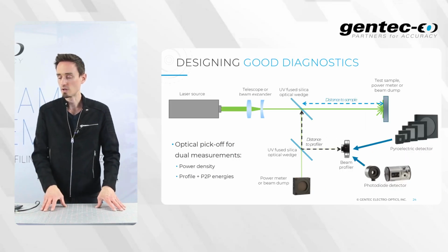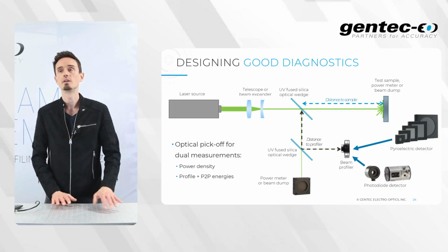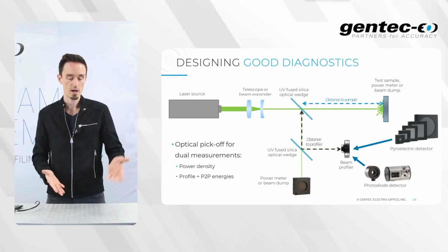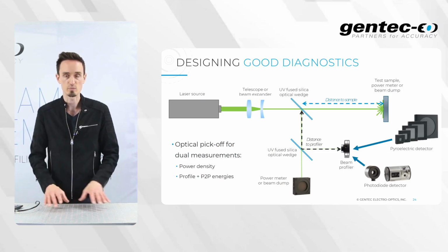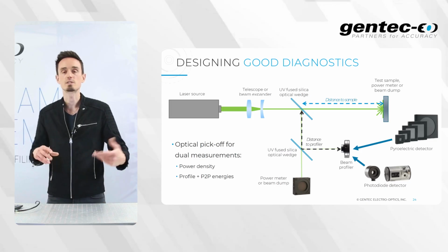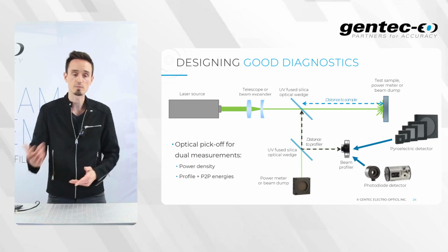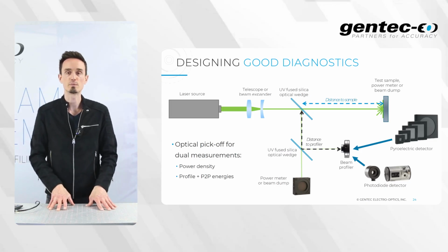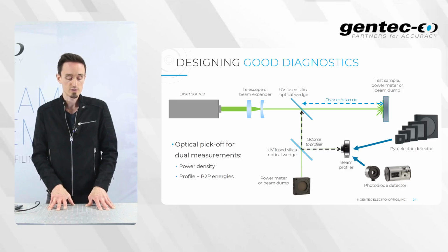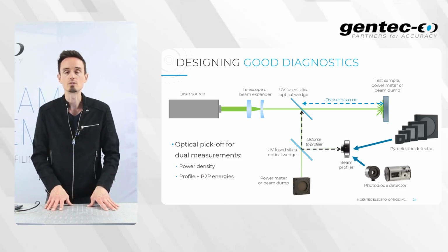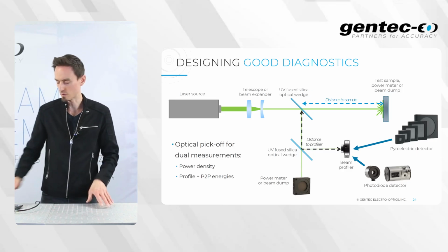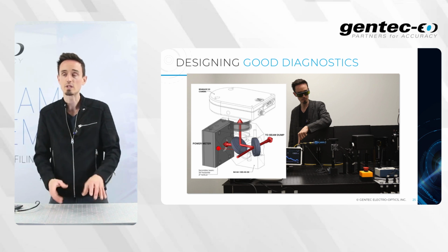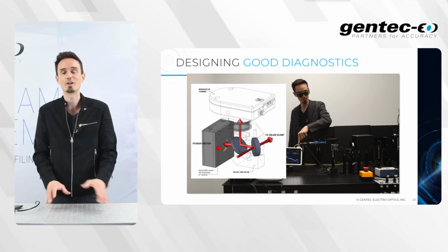An example of a good optical pick-off, pretty standard setup here with two wedges, semi-transparent mirrors, where you could place various types of detectors, beam dumps, pulse-to-pulse energy measurement, beam profilers, and so on. Goal is to have an inline way to measure the power or energy at a decreased level. And there are some compact systems. Yes, sometimes we do get in a lab and run some measurements with those.